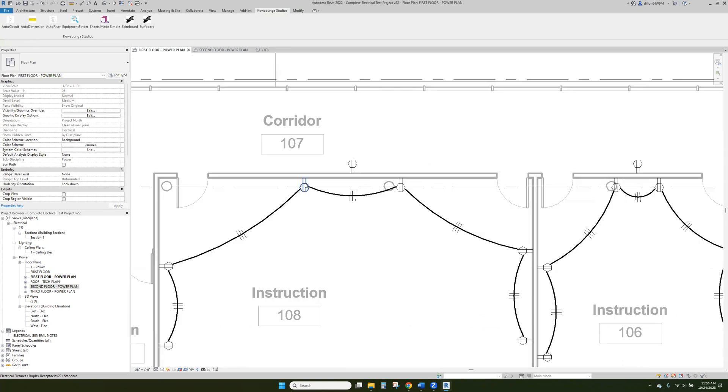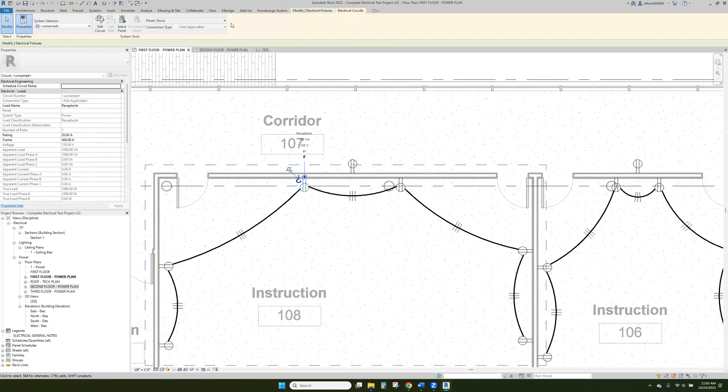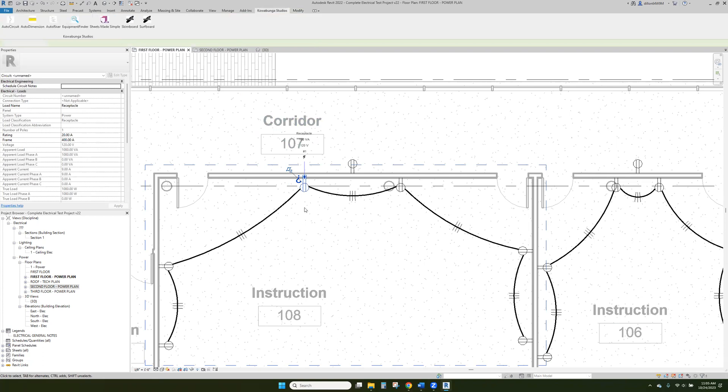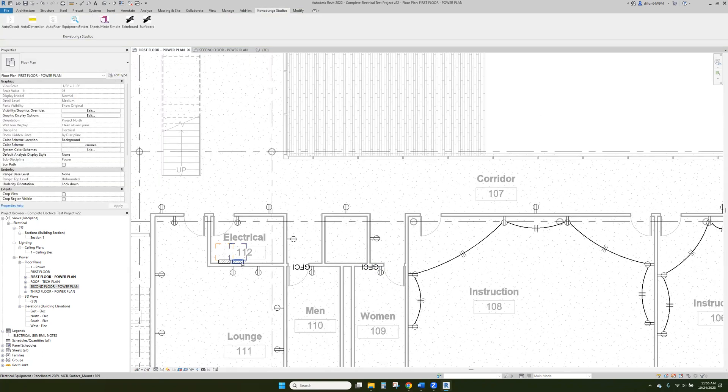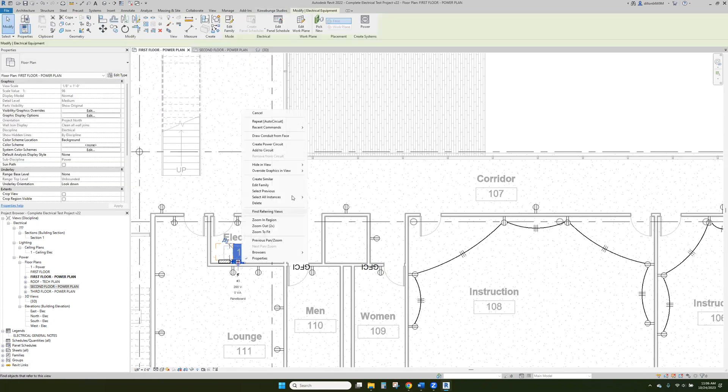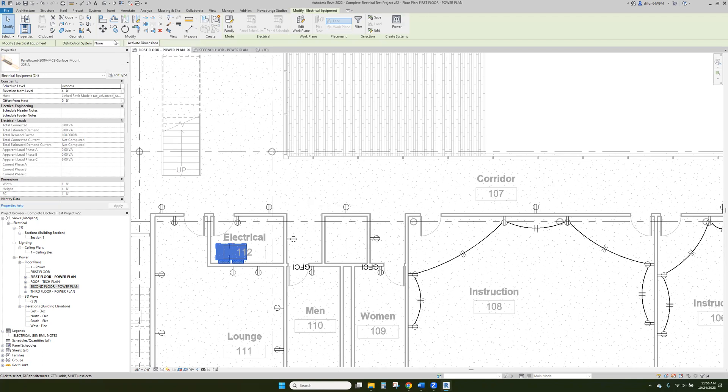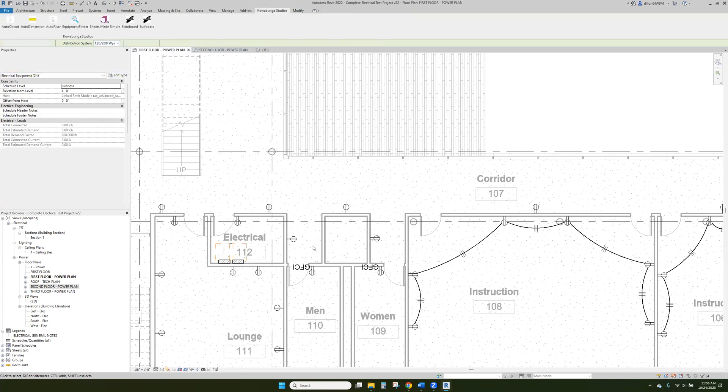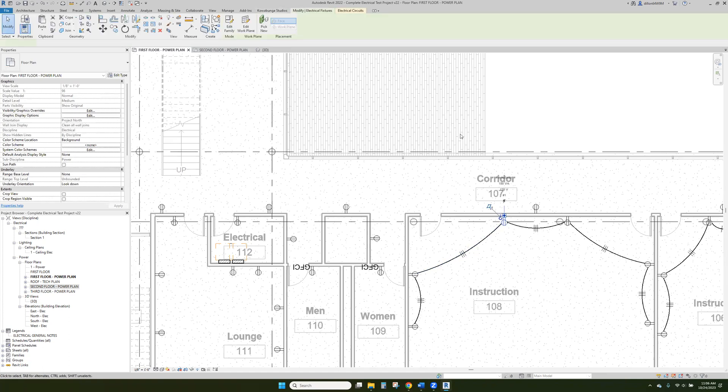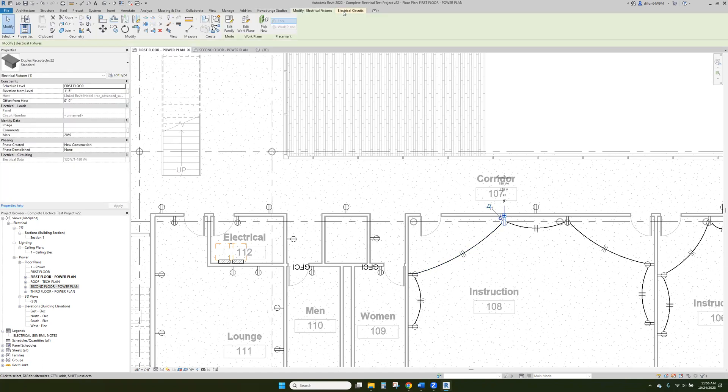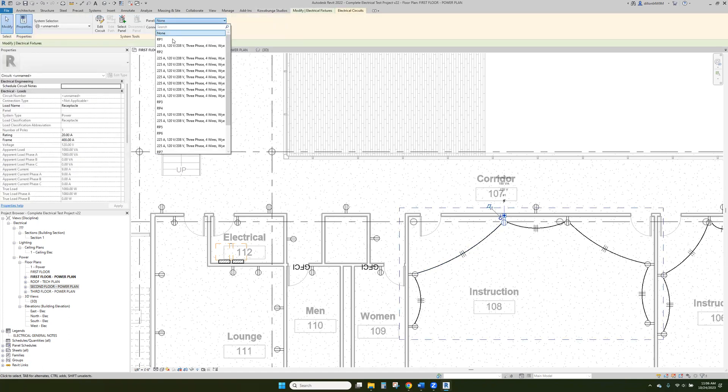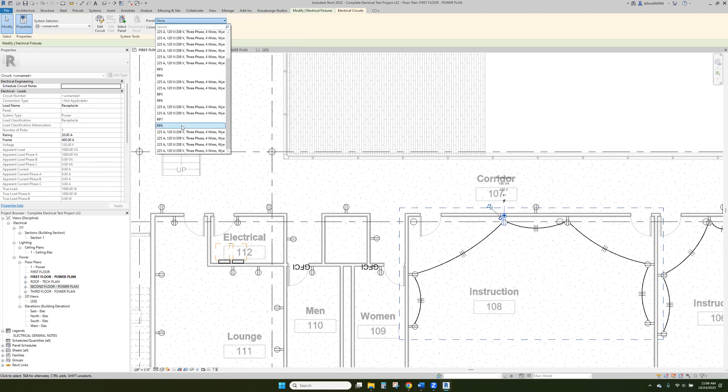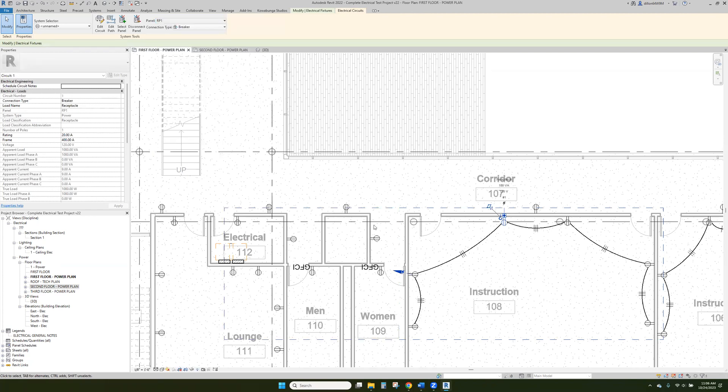And then we need to be able to go in here and create a circuit. So a couple things with this, and I'll just select all our panels in the project. We'll need to assign them a distribution system. So go ahead and do that. And now we can circuit these to our panels. So here's the ones that we've named through. So just circuit to RP1, which is awesome.